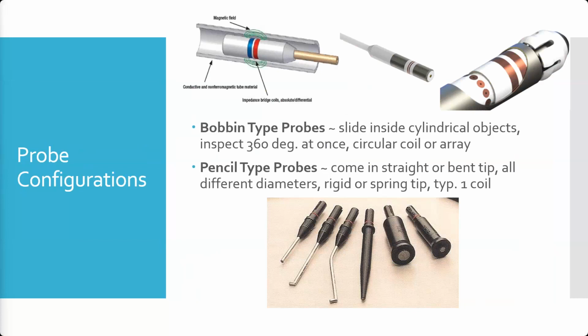The bottom one here, pencil type probes, they can come in all different configurations. So we have probes that are similar to these, where it's just one tiny little coil on the tip. And then we've got these spring rollers. These are considered a pencil probe, even though they don't look as pencil-like. It's a small coil that is placed on the surface. Those just happen to have that spring device in there that helps it maintain contact. So those are the different configurations of probes.